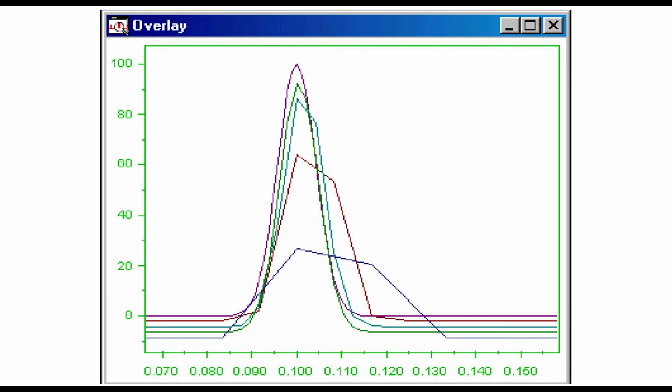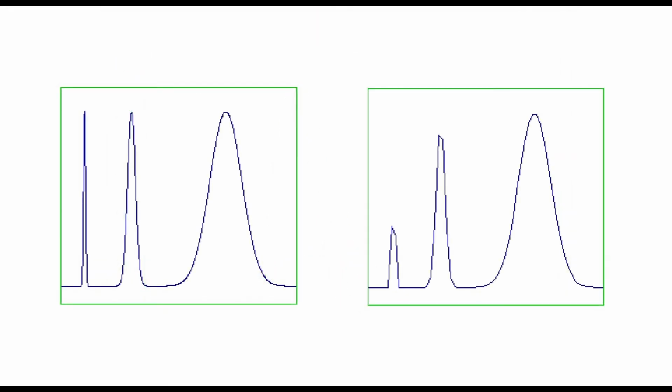The degradation of peak shape depends on the relationship between the sampling rate and the peak widths. The following figure shows two chromatograms, sampled at 16 and 1 samples per second. The first peak is the same as in the previous figure and is quite degraded. The second peak is 4 times as wide as the first and is only slightly degraded. The third peak is 4 times as wide as the second and is hardly changed at all. Even at the reduced sample rate, the third peak still has over 20 data points across its width.